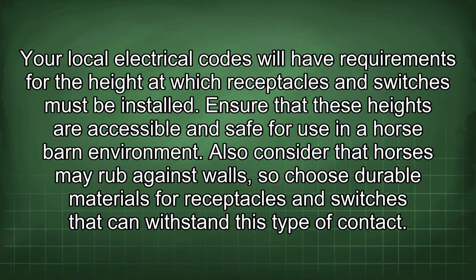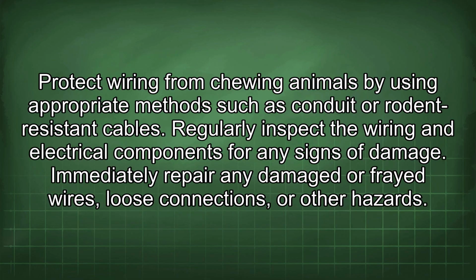Your local electrical codes will have requirements for the height at which receptacles and switches must be installed. Ensure that these heights are accessible and safe for use in a horse barn environment. Also consider that horses may rub against walls, so choose durable materials for receptacles and switches that can withstand this type of contact. Protect wiring from chewing animals by using appropriate methods such as conduit or rodent-resistant cables. Regularly inspect the wiring and electrical components for any signs of damage. Immediately repair any damaged or frayed wires, loose connections, or other hazards.